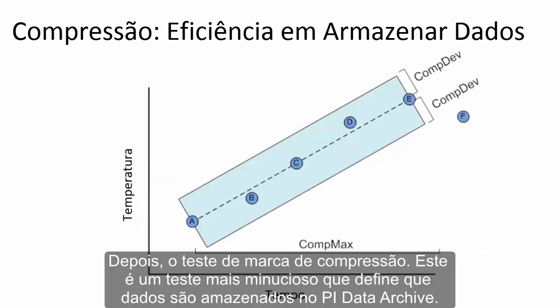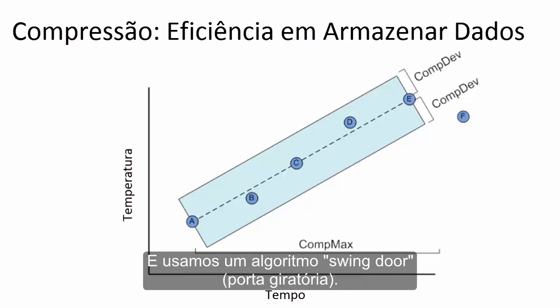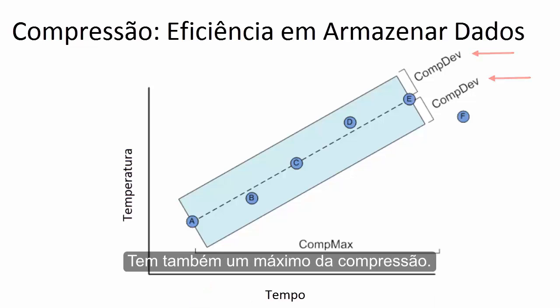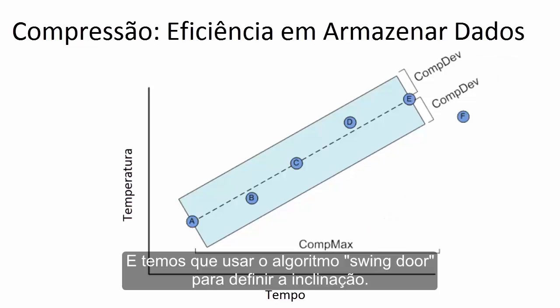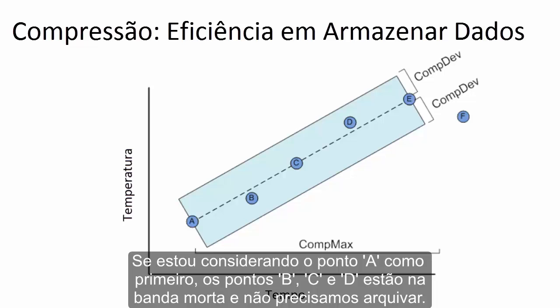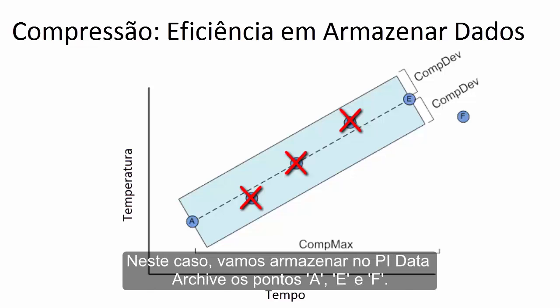Next is the compression marking test. This is a more thorough test that defines which data is stored in the PI Data Archive. Unlike exception, compression can have a slope, and we utilize the so-called swing-door algorithm. In terms of PI Tag attributes, we have compression deviation which defines the dead band, compression maximum, and the slope of the data is handled using the swing-door algorithm. If point A is the first point, points B, C, and D are within the dead band and don't need to be archived. Point E is the last point and point F falls outside the dead band, so what we store in the PI Data Archive are points A, E, and F.